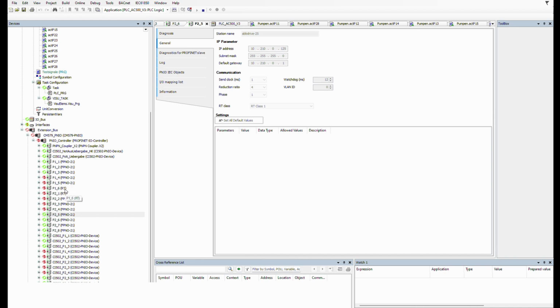So once the boring process has already reached that status and the pump is connected, it will be automatically detected via the Profinet scan of the AC500 with a MAC address scan, and then the user at the tunnel tells the AC500 this is pump 1.4, and then it gets parameterized automatically.